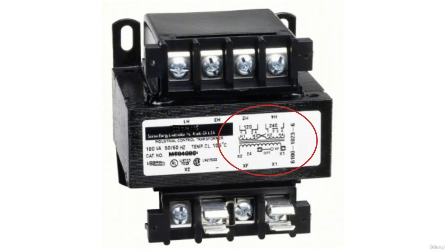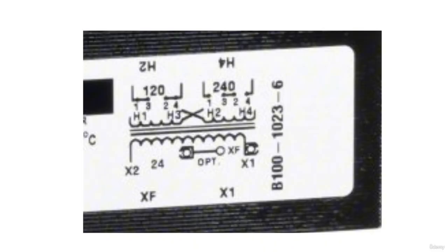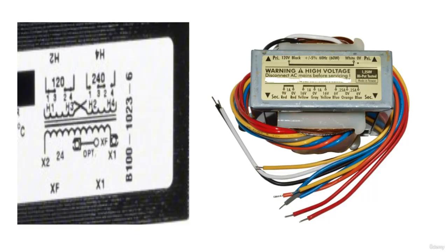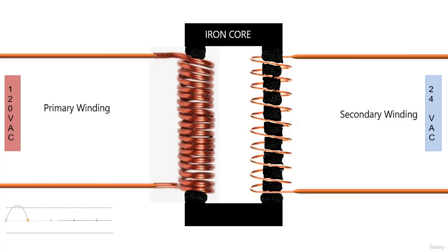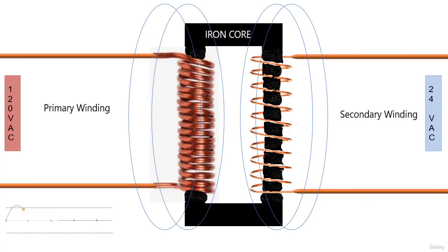It's important to read the transformer voltage taps to ensure we apply the correct voltage and create the correct voltage. You can have multiple taps on both the primary and secondary for multiple voltages. The alternating current in a transformer is what helps create its resistance. But in inductive loads, where we are inducing work using a magnetic field, the resistance is called impedance.